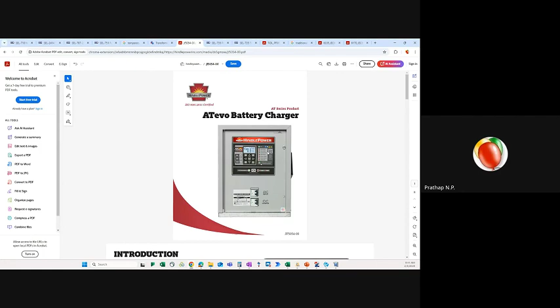But now these guys have communication capability. So it has serial communication. It has Ethernet-based communication. It also has IEC 61850 communications. So now this battery charger can report a lot of information. What is the battery status? What is the voltage of each individual cell? Because it's usually 2 volts every cell. So to make 125 volt, you at least need 60 to 65 cells. We keep it 65, so the total is 130 volt, just in case it drops to 125 volts, and we can keep it operational.